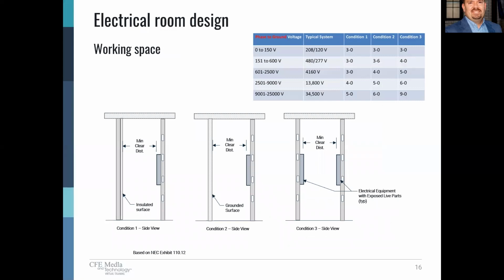So here's a visual representation of the 3 conditions that we discussed in the previous slide. So condition 1, if we look at the side view, in this case, a panel board. What is across from the panel board? Condition 1 is an insulated surface, such as drywall, for example, would serve as an insulated surface. Condition 2 is a grounded surface directly across from our equipment on the other side of the working clearance. So that would be concrete or masonry, for example. Condition 3 is electrical equipment directly across from electrical equipment, where you could have the condition of exposed live parts on either side. And so as you can see in the table at the top of the slide, you can see how each condition then implies a different requirement for the depth of the working clearance.